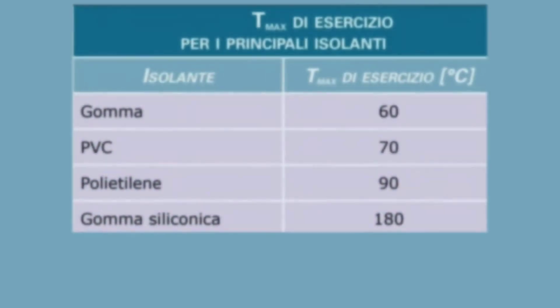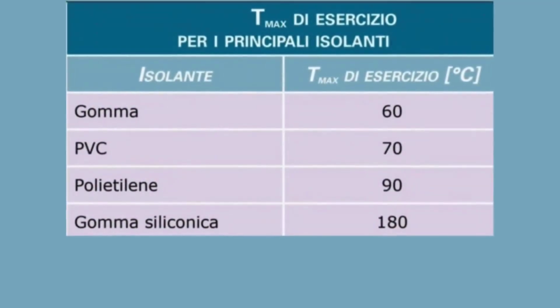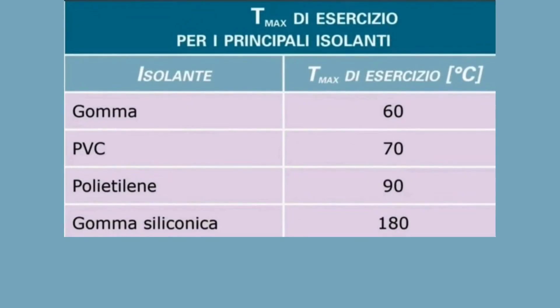Insulation materials such as rubber, PVC, or polyethylene have specific temperature limits, and exceeding these limits can significantly reduce the life of the cable. For example, rubber insulation can withstand up to 60 degrees, PVC up to 70 degrees, and polyethylene up to 90 degrees. If these temperatures are exceeded, the performance and safety of the cable will be affected.